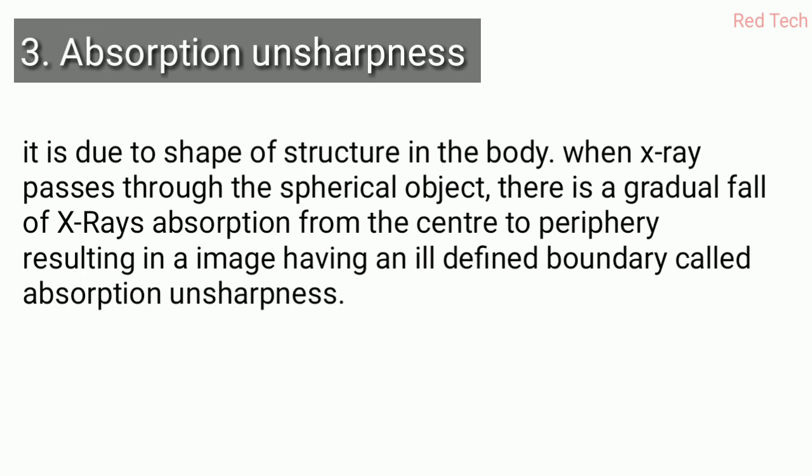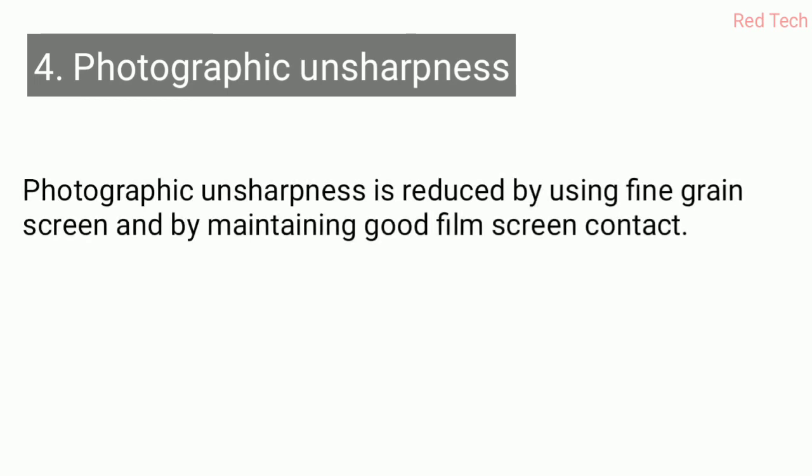The fourth type is photographic unsharpness. As the name suggests, this is related to the film. It is reduced by using fine-grained screens and by maintaining good film-screen contact. Maintenance plays a key role in reducing photographic unsharpness.